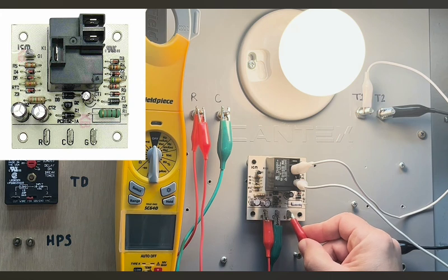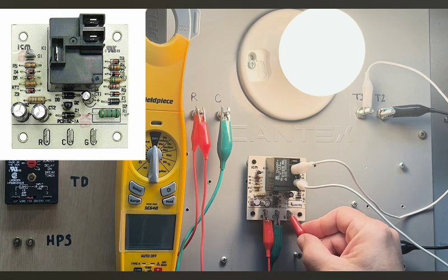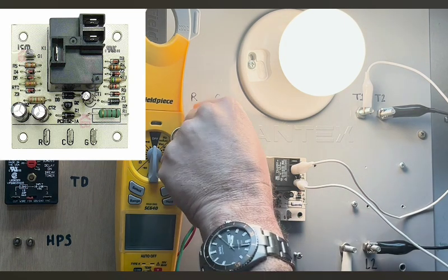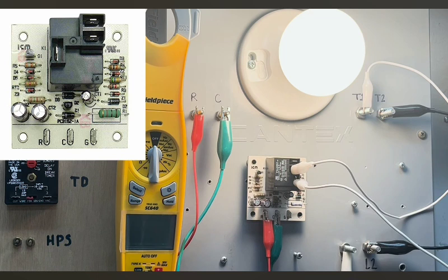Now, here's why this board is important. If I wanted to get more efficiency and save a little bit of money and get more comfort out of my evaporator coil, once I lose the G call, the relay is still closed. Now it's closed for 50 seconds. We're going to demonstrate that off time here in a little bit.